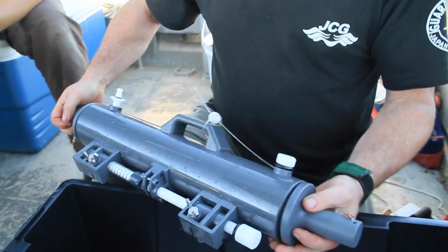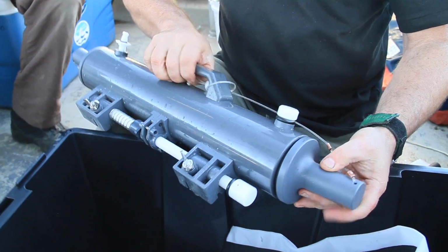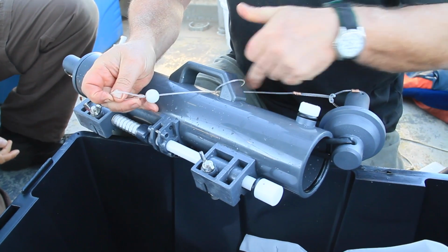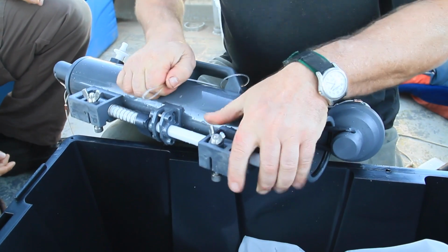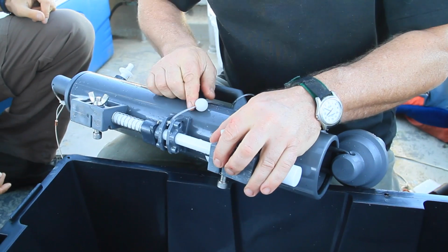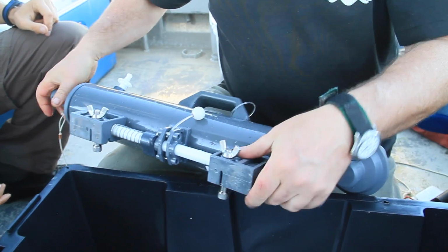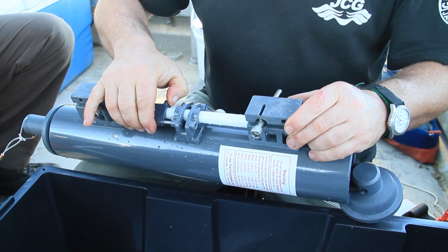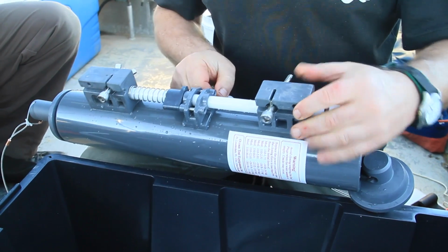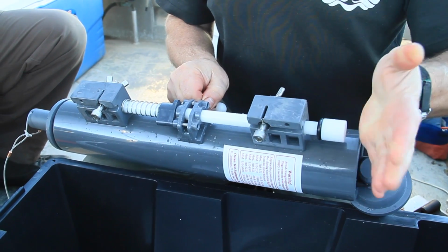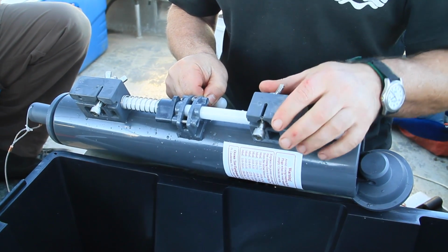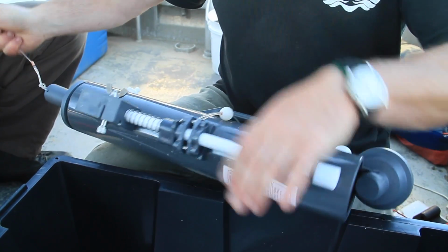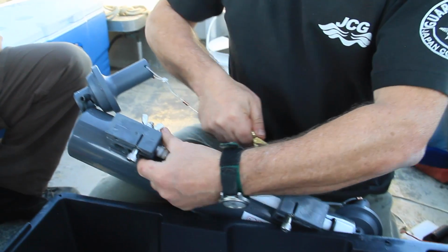Okay, so to prepare this bottle, we have to cock it. So basically, open the top, pull the lanyard through the handle, and it goes into the clip like that. There are 2 clips on this one. You see that there are 2 metal posts here. One of them moves on the slider, and the other one moves with the rod and the piston on it.